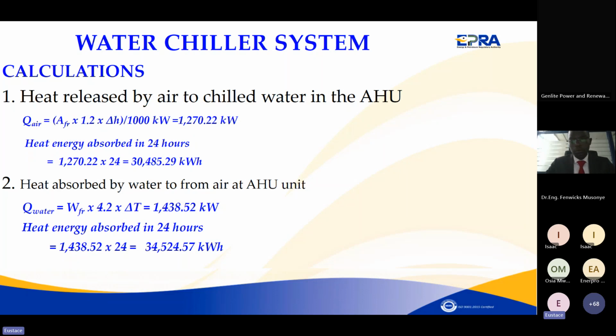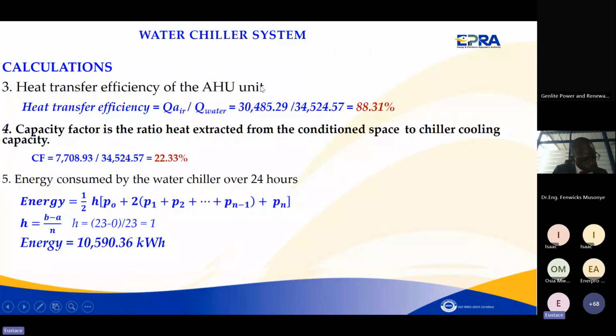Also, there is probably poor heat transfer due to the dirt, or poor heat transfer because of the insulation or resistance of the cooling coils. And in that case, you are supposed to calculate the effectiveness or the heat transfer efficiency of the AH units. And in that case, you can see it's 88.31%. And probably you can try to improve it by doing a cleanup of the cooling coils. You check whether at the time you were doing your measurements they were dirty or not. You can clean them and continue and see whether it's going to improve.